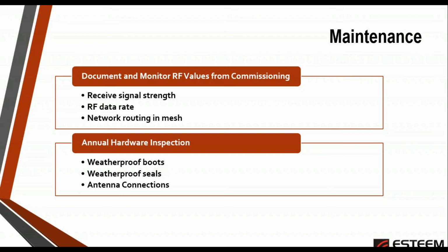Because if it used to be -60, we have a problem. If it's always been -80, there's really no problem. So a number by itself doesn't mean anything—it's the number over time that tells us things. That documentation from site commissioning is key, because we need to look at signal strength, data rate, and the actual network routing. It may be we're never utilizing a repeater site we put in for redundancy as an alternate path, and it's always been running that way, not necessarily as you'd expect.